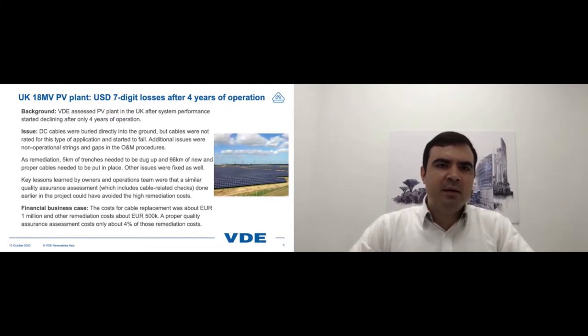of an 18 megawatt power plant in the UK, where VDE assessed the power plant after system performance started declining after only 4 years of operation. The issue was that the DC cables were buried directly into the ground, but they were not rated for this type of application and started to fail.